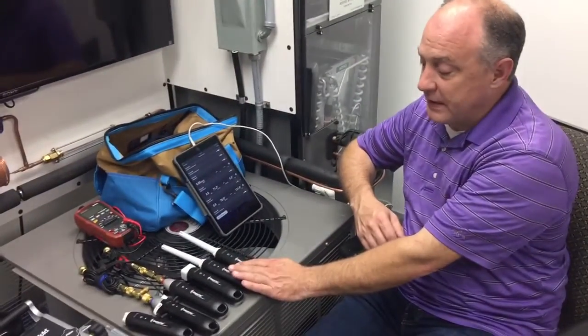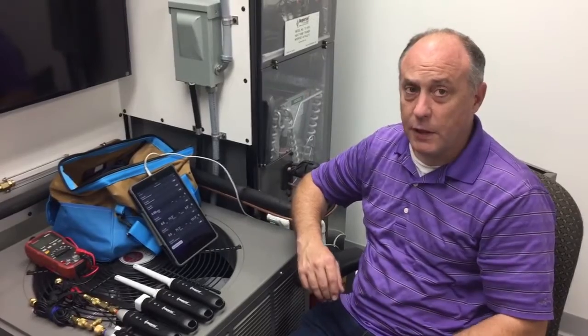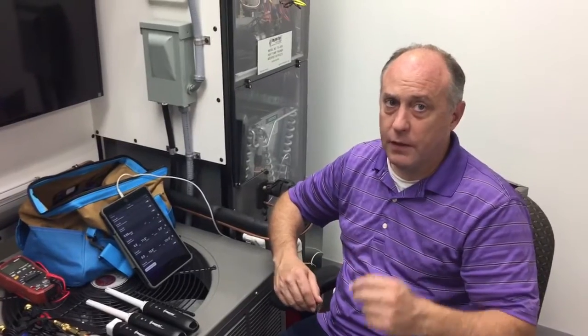Now, once you map probes, that mapping stays there until you change it. So this is a one-time process, but what you're doing is telling the iManifold system what every probe in the system is responsible to do. And then once you have it set up and configured that way, it's very easy to manage, because literally all you do is turn on the iManifold, turn on the probes, they come into the network and they're doing what they're supposed to do. But the cool thing is, if I'm down at the condensing unit and I realize I got my return and my supply probe reversed in the ductwork, there's no having to go back in the house to change that. All I do is simply remap the probes and I'm good to go. So this gives you an idea of how we map in wireless probes on our Zigbee network, and hopefully that gets you through the process.